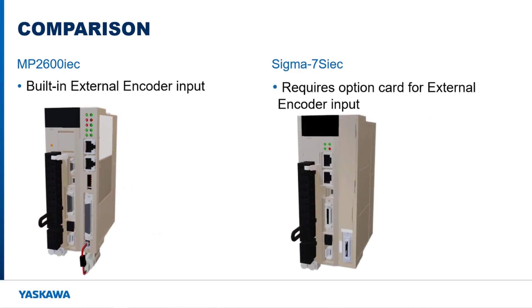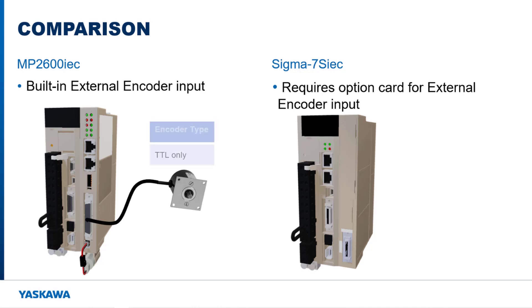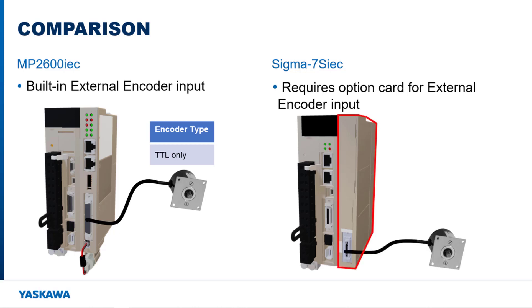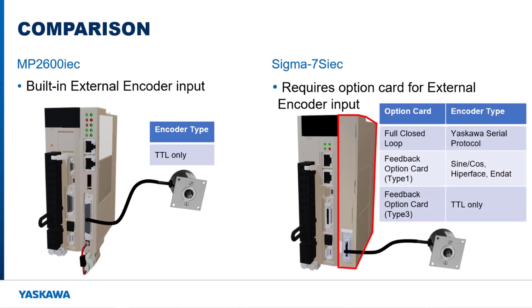External encoders are available on both controllers. The MP2600iec has one built in to the controller, no option card needed. This input only works with TTL encoders. The Sigma-7S IEC needs an option card to have an external encoder input. Three cards are available for different types of encoders. External encoders are needed for dual feedback applications.